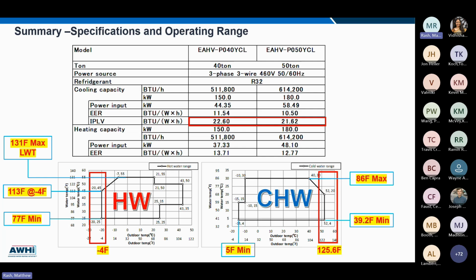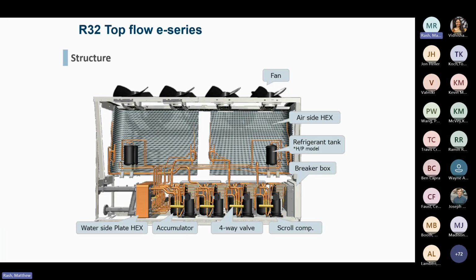It doesn't have quite as high capabilities on the heating side, down to -4, with leaving water temps that are a little bit lower. So it's up to a max of 131. But there are some trade-offs there with hot water temps versus efficiency on the cooling side and high IPLVs, which we're able to achieve with this. So you'll see IPLVs well above 21 for the 40 and 50 ton unit. And again, you've got that hot water heat pump capability. It's not simultaneous, so it's changeover. But for things like domestic hot water preheat or summer VAV reheat, if you're tying this into a 4-pipe network, it's perfectly suitable for some of those applications.